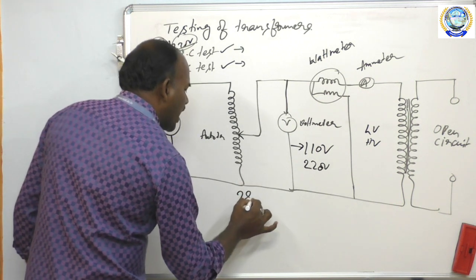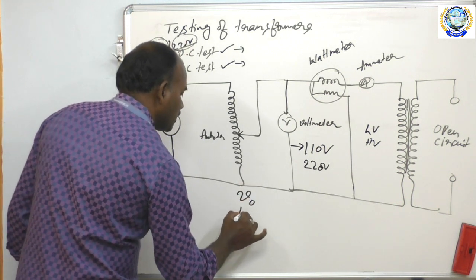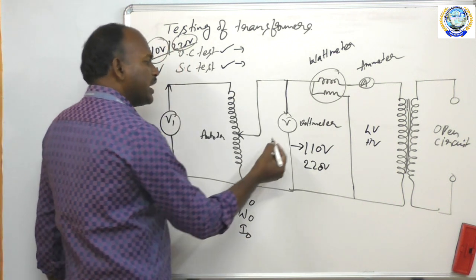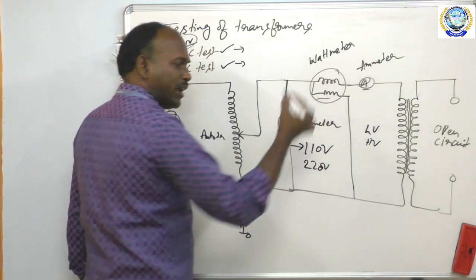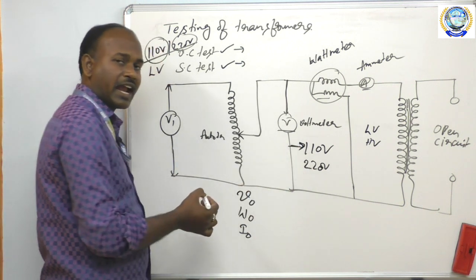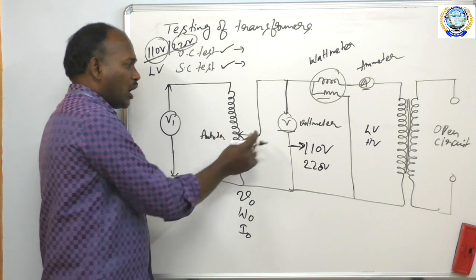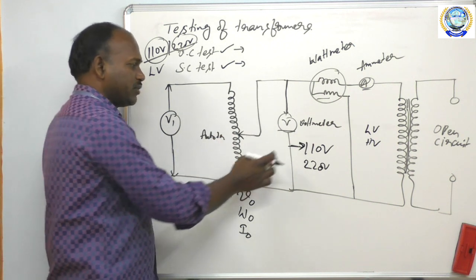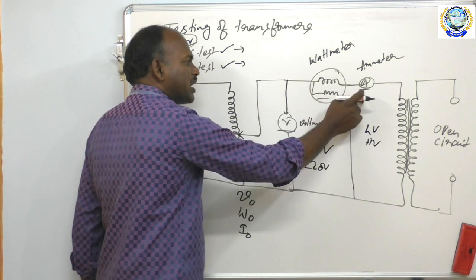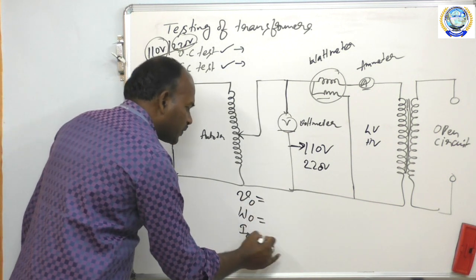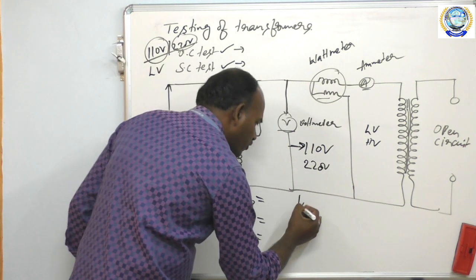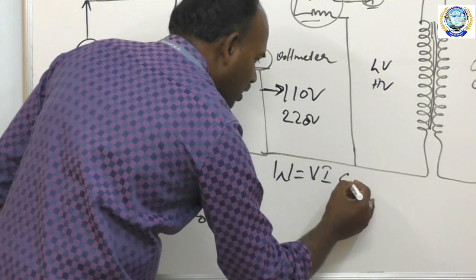You will get the values of V0, W0, and I0 by observing the readings of the voltmeter, wattmeter, and ammeter. Vary the auto transformer until the voltmeter reads 110V, then take a set of readings. Using the formula W = VI cos φ, from the wattmeter reading W, voltage V, and current I, you calculate the value of cos φ.